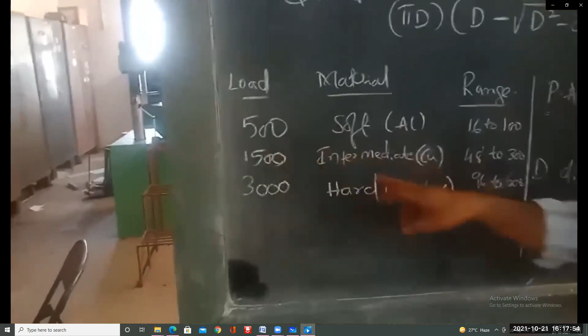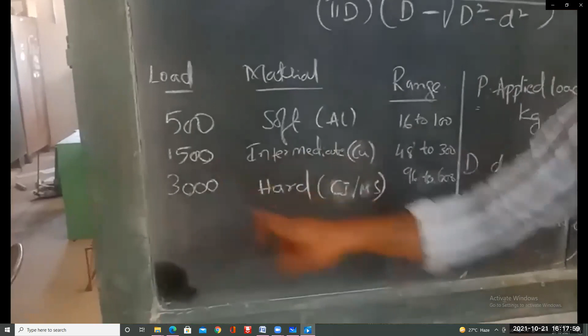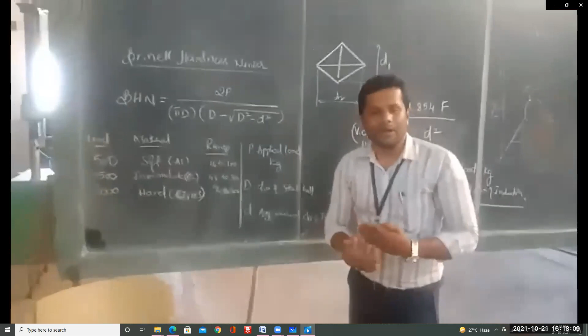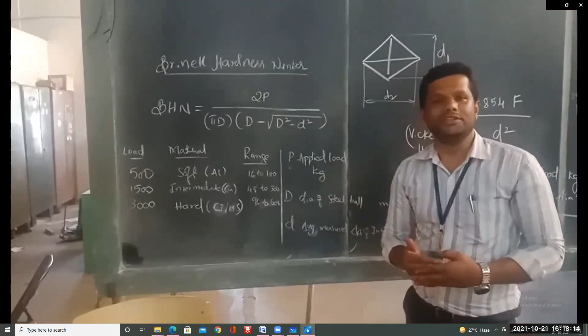For different materials we apply different loads. For example, for aluminum we apply a load of 500. Brass, an intermediate material, like copper, brass and bronze, 1000 to 1500. And for hard materials, cast iron and mild steel, we apply a load of 3000. With this force, you repeat the procedure as with the brass material, and we conduct the test once again. We do the experimentation.